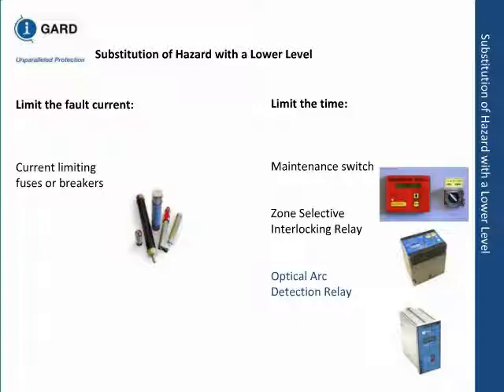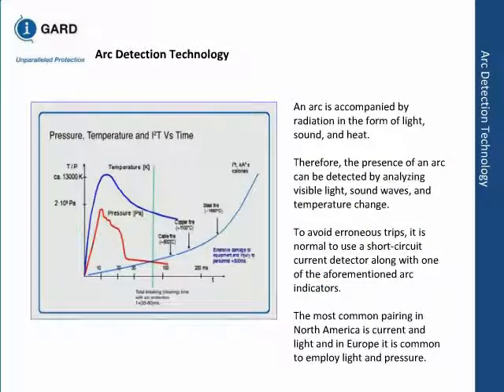Okay? Now, anytime an air break breaker opens or closes, it will have an arc. You don't want it to trip every time it's doing its normal job. So to provide a backup, you have a current input through it. That means two conditions have to be satisfied before the breaker trips. Current has to go to a very high value, and flash has to happen at the same time, which will allow the breaker to trip. You can set it up as multi-layer. You can have it so that it only trips some of the feeder breakers, or you can trip the whole thing. That's up to you. But this is a very fast method. It will cut down the incident energy.